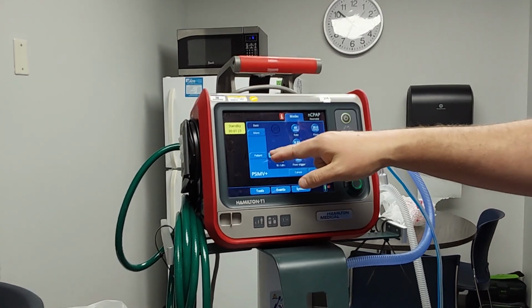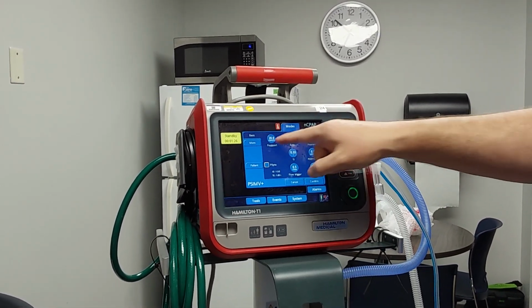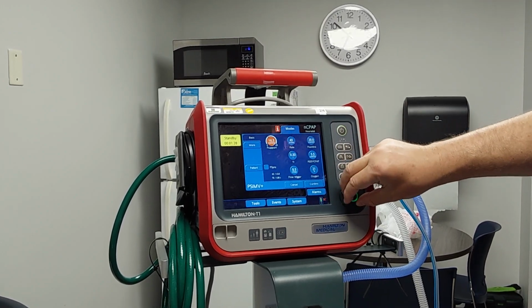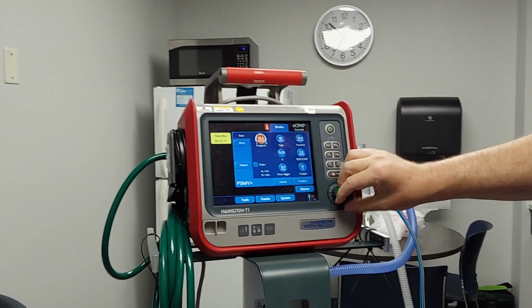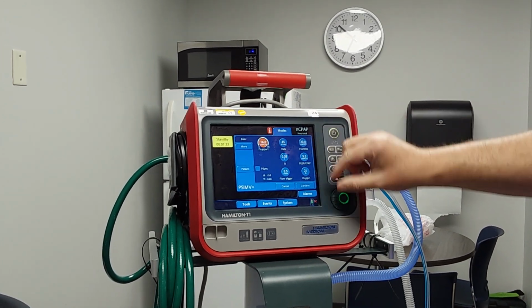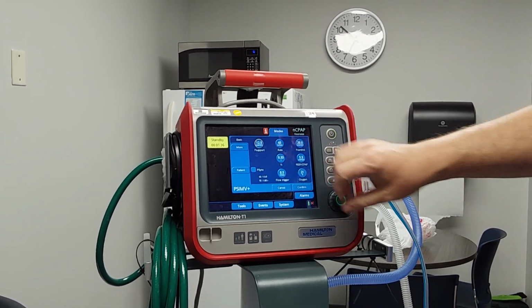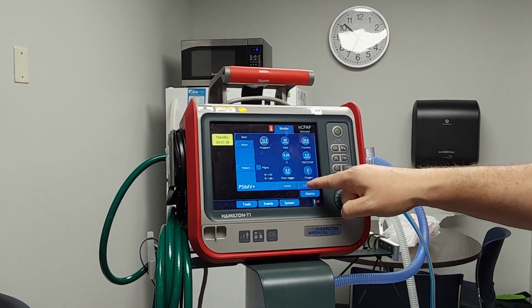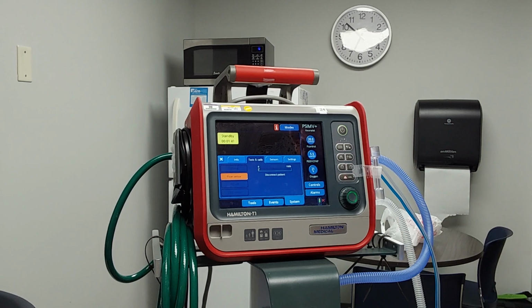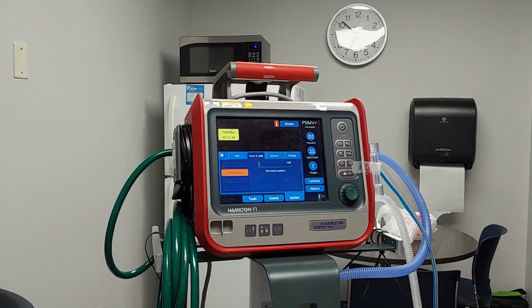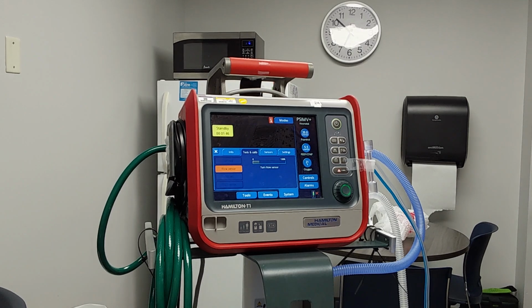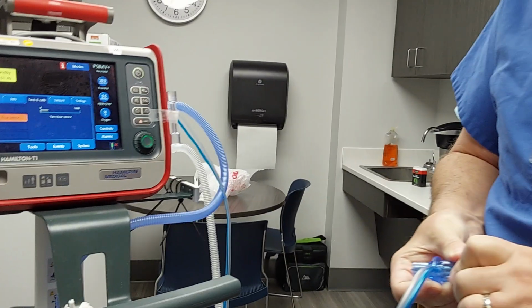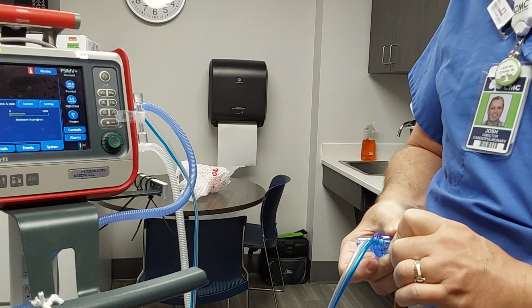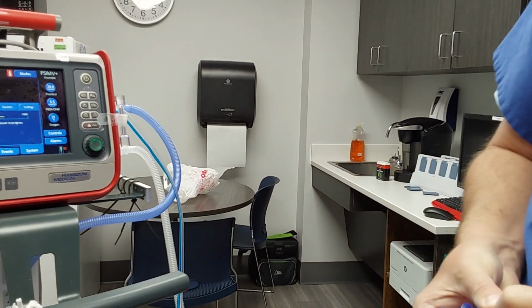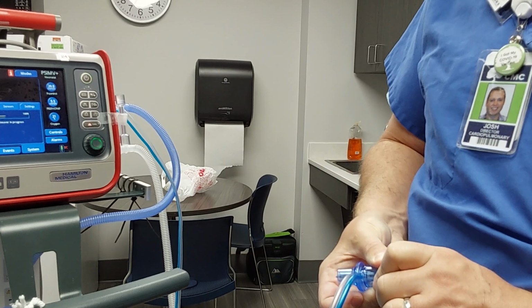P-Sync. So if you want to dial in your pressure support, uncheck your P-Sync and you can actually dial in pressure support. So I would turn it less than your pressure control. We're going to calibrate our flow sensor. Just follow the directions. That part I haven't mastered. I always have to use that little white thing that comes with it. It makes it easier. I didn't want to untape it though.